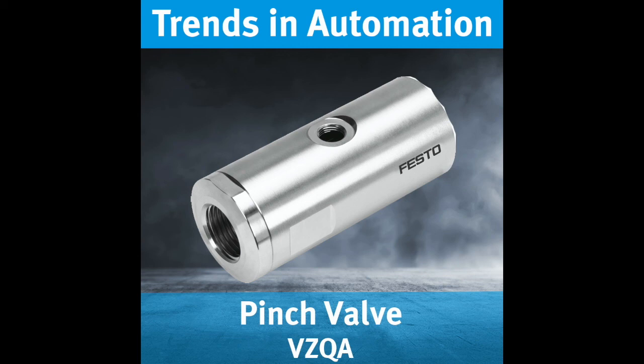Our normally open pinch valves are now offered in 1/4 inch, 1/2 inch, and 1 inch sizes. The normally closed versions are currently available in 1/4 inch and 1/2 inch sizes, with the 1 inch release slated for next year. It's also worth noting that while the normally open version is available with all 3 sleeve materials, NBR, EPDM, and silicone, the normally closed variant can only be ordered with the EPDM sleeve. This can be a key topic when discussing chemical compatibility and FDA compliance.